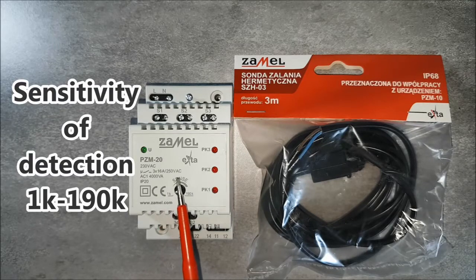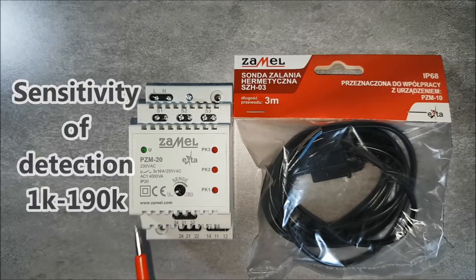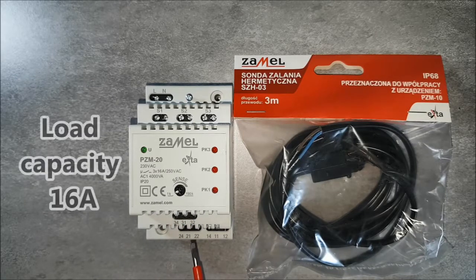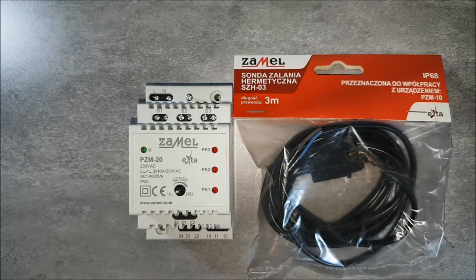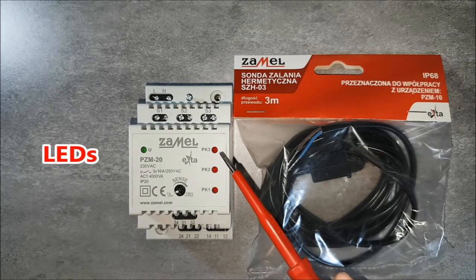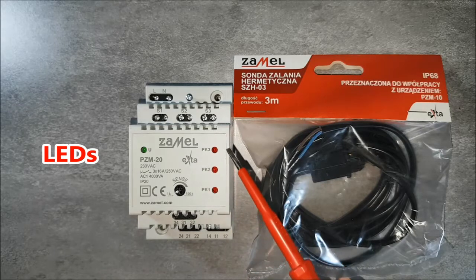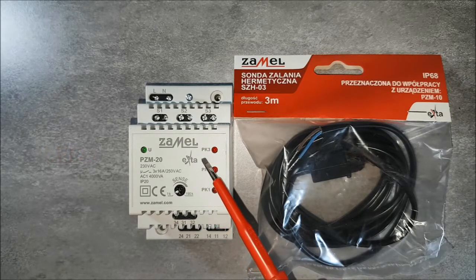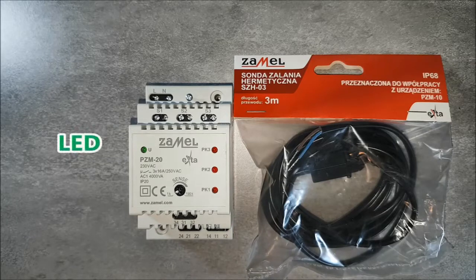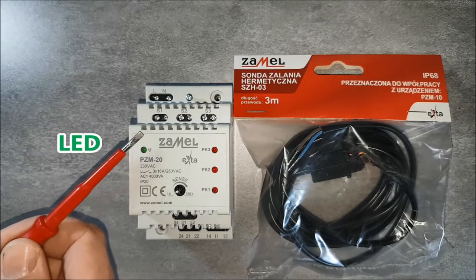Probe sensitivity level can be set in the range of 1 to 190 kΩ by the front panel potentiometer. The device output has 3 relays with a maximum contact load of 16 amps. The use of NO and NC changeover contacts increases the application area of the PZM-20 relay. Current status of the outputs is indicated by red LEDs, PK1, PK2 and PK3. Green LED signalizes the presence of 230 VAC supply voltage.